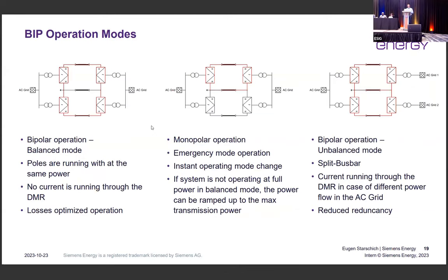A very quick one on the bipolar operation modes. The bipolar system has a lot of flexibility. The most common operating mode, as we call it, is a balance mode. That means we have the system being connected at one side and at the other side to the same AC grid. In balance operation, we have no current going through the DMR, the dedicated metallic return. This is, let's say, the losses optimized operation.